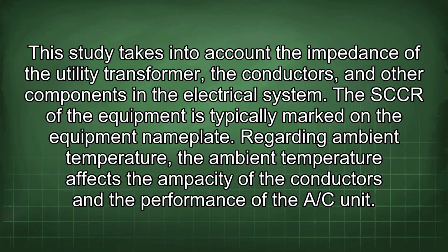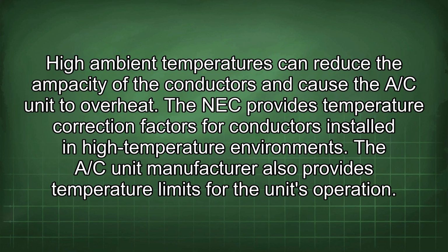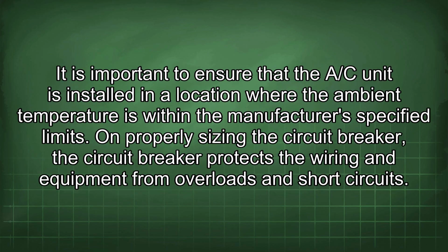Regarding ambient temperature, the ambient temperature affects the ampacity of the conductors and the performance of the A/C unit. High ambient temperatures can reduce the ampacity of the conductors and cause the A/C unit to overheat. The NEC provides temperature correction factors for conductors installed in high-temperature environments. The A/C unit manufacturer also provides temperature limits for the unit's operation.